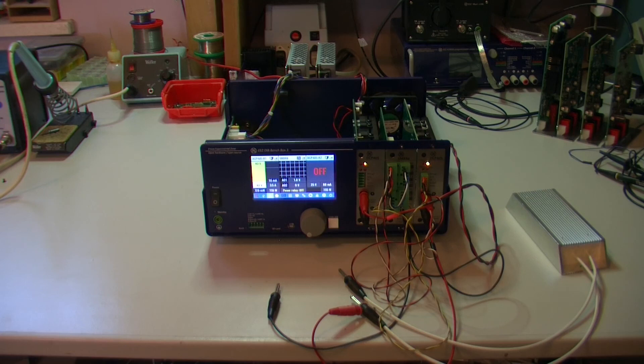This test procedure includes all important parts of DCP405. And something that is missing is the calibration of voltage and current. And for that we will need some high-precision digital multimeter module or some external digital multimeter with some USB or Ethernet for SCPI communication.